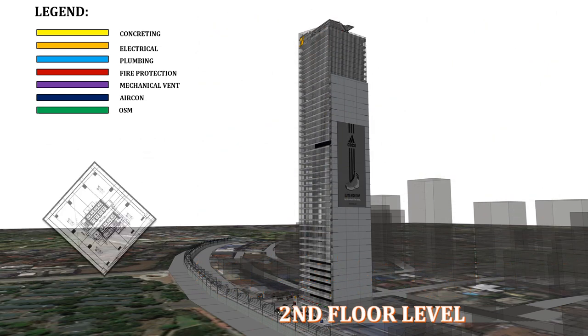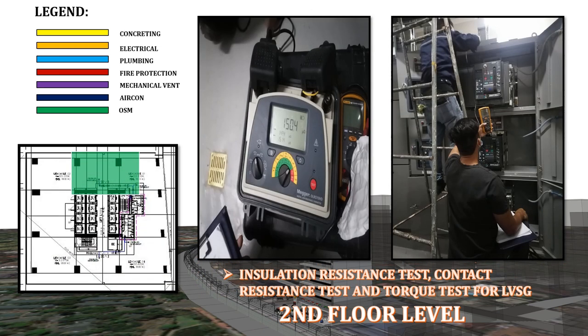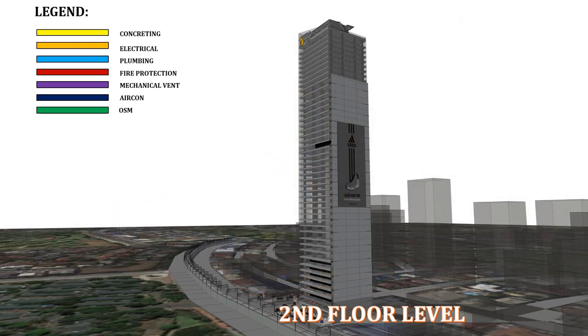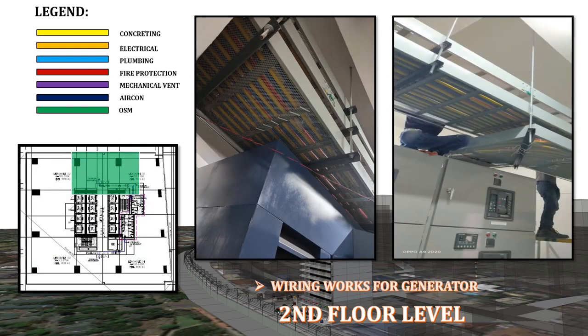At substation works, the accomplishments at second floor level is the insulation resistance test, contact resistance test and torque test for LVSG. At generator works, the accomplishments at second floor level is the wiring works for the generator circuit breaker.